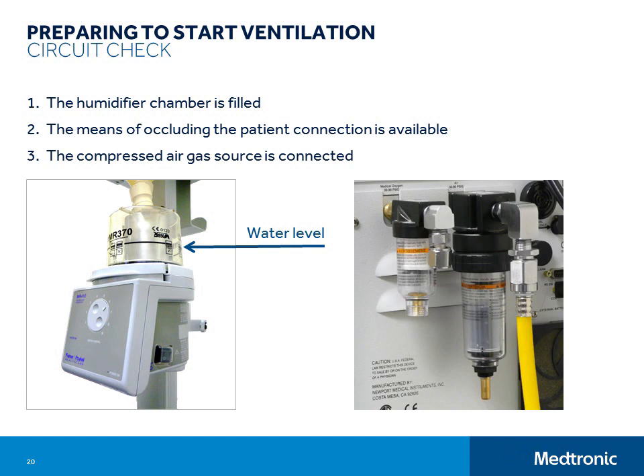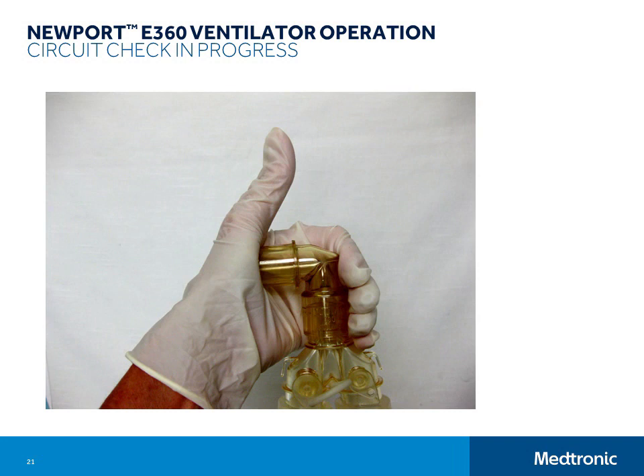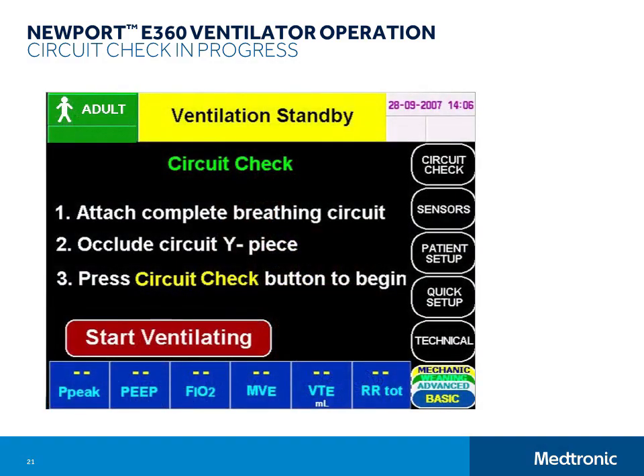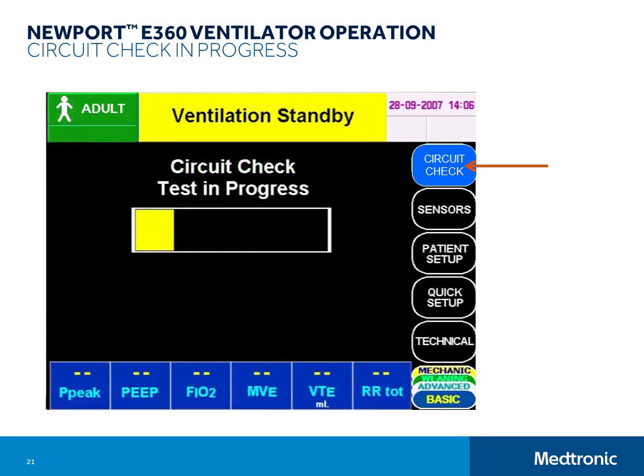Okay, let's start. For the first half of the circuit check, you will need to use a gloved hand or cap or another means to fully occlude the patient connection of the circuit. Wait until the circuit stops moving, then touch the circuit check button. If the resistance in the circuit system is very low, there won't be a second step and the circuit check results will appear on the screen. If the screen indicates the need for a second step, you will need to unblock the Y before touching circuit check to initiate that step.